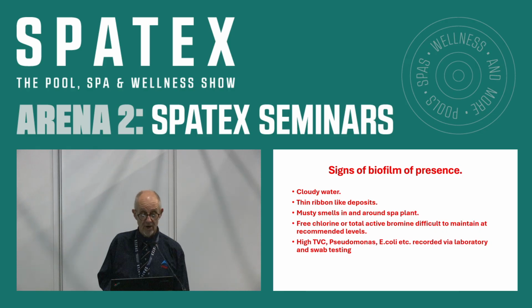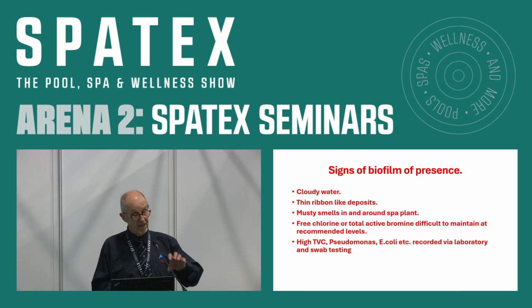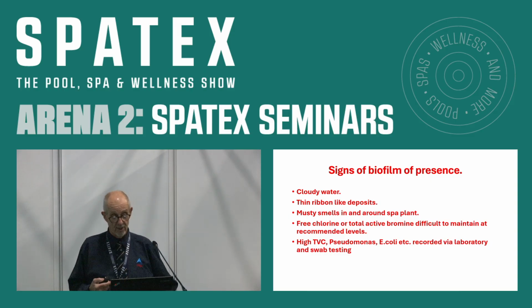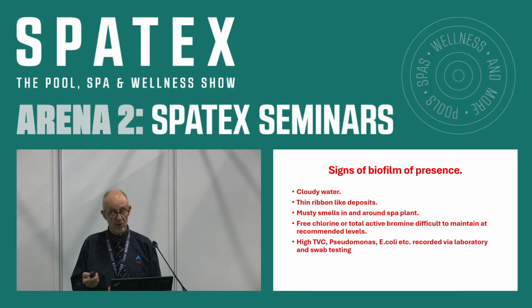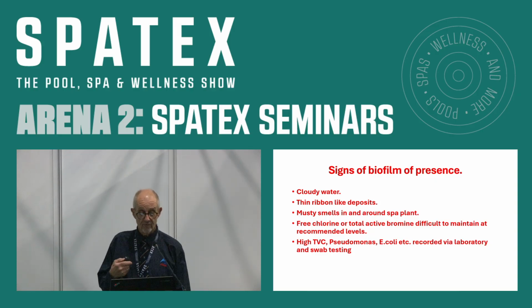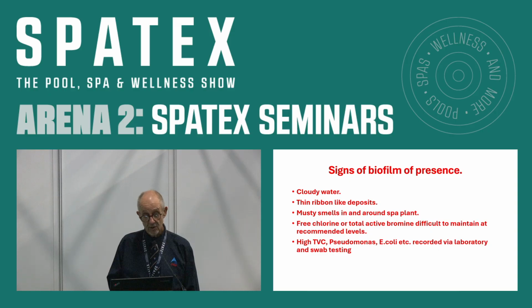Signs of biofilm present: cloudy water, thin ribbon-like deposits in the water, musty smells in and around the spa plant and the spa itself. Free or total active bromine, difficult to maintain to recommended levels because it's been eaten up by the biofilm. That's one of its properties. High TVCs, Pseudomonas, E. coli, recorded via laboratory and swab testing.